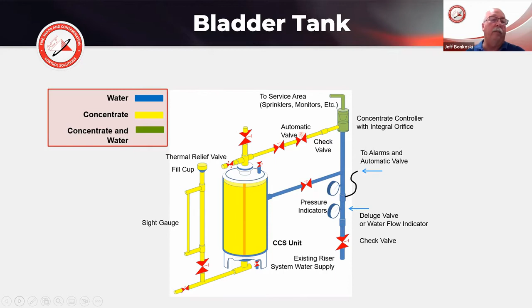So when we look at our bladder tanks, the water activates when the sprinkler goes off, pushing against the bladder, squeezing it, and forcing the concentrate up through the controller into whatever the mixed rate is. The water comes up out of the pipe, through the different check valves, and is introduced into the water stream.